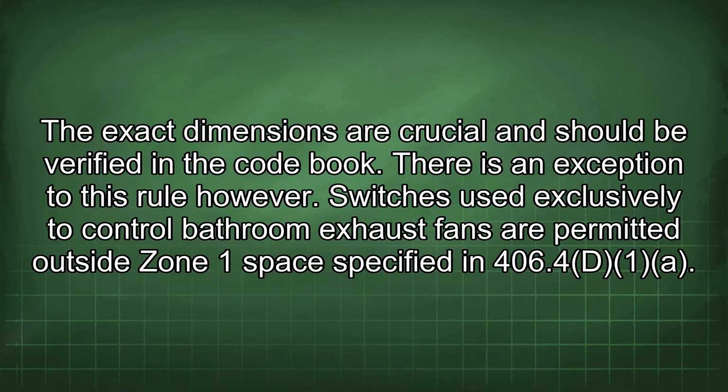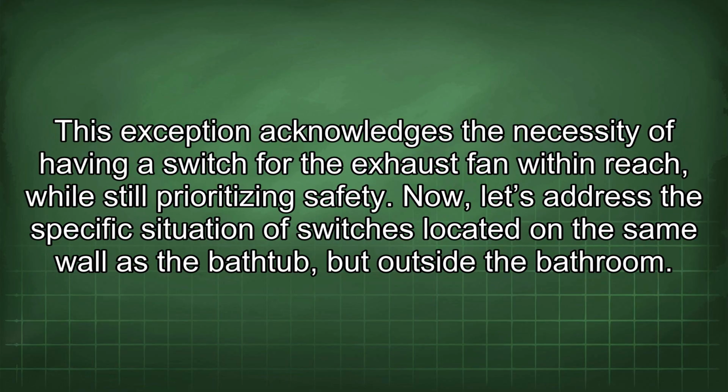There is an exception to this rule, however. Switches used exclusively to control bathroom exhaust fans are permitted outside Zone 1 space specified in 406.4d. This exception acknowledges the necessity of having a switch for the exhaust fan within reach, while still prioritizing safety.